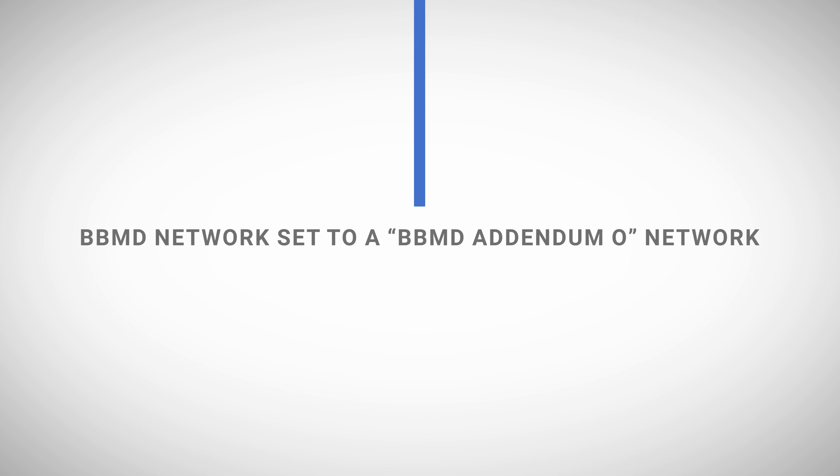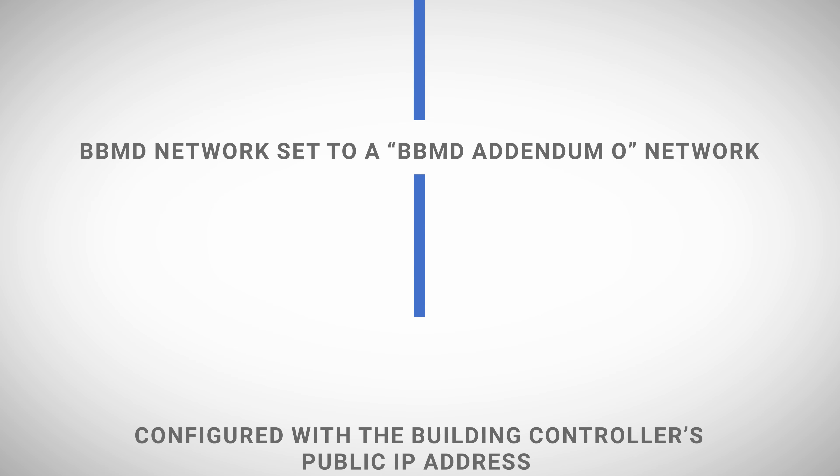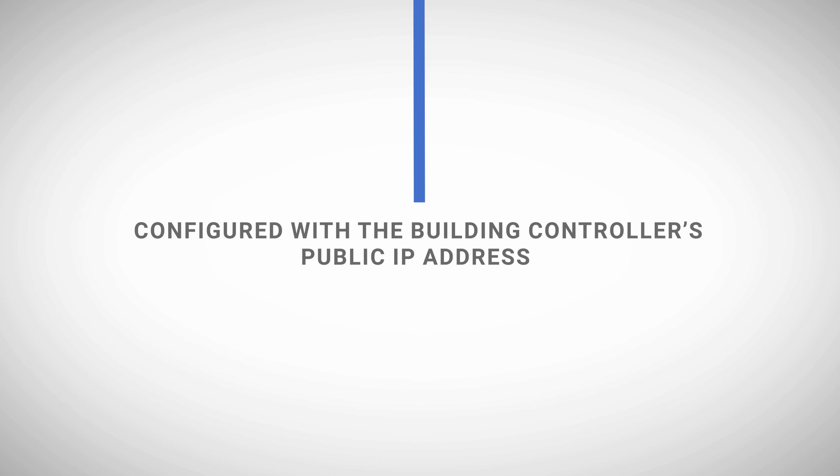But with ASHRAE BACnet standard addendum O, you can create a BACnet system through the internet even when port forwarding is being used. To do so, each building controller that is configured as a BBMD will need to have its BBMD network set to a BBMD addendum O network, and then the BBMD addendum O network configured with the controller's public IP address. The public IP address is the public address of the IP gateway through which the BBMD connects to the internet.